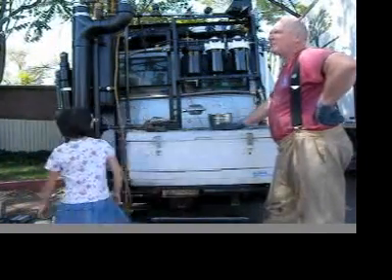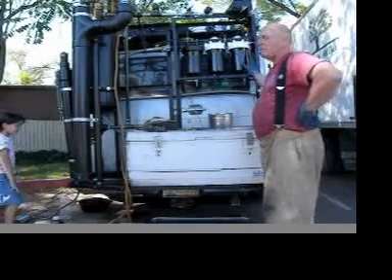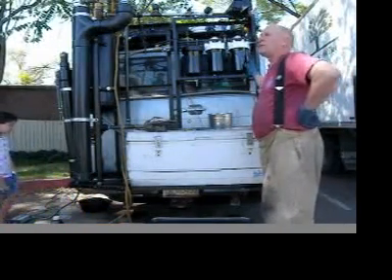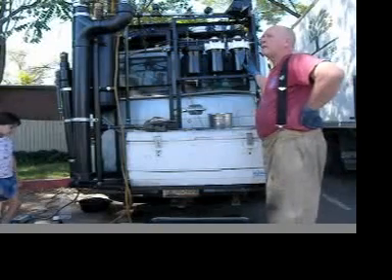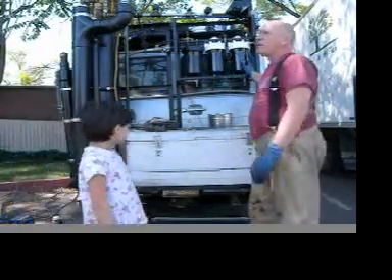We're processing at maybe 2 PSI. These filter cartridges can handle a 20 PSI pressure drop across them, so I can take the pressure up to 20 if I want to.